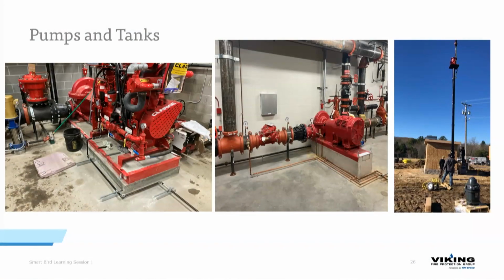On the left here we have a diesel fire pump. Again, extra consideration. Diesel, you need a tank. You usually need containment on that tank. You need exhaust. You need batteries for startup. You need a diesel mechanic there on a yearly basis to change the oil. Every fire pump requires some level of testing, and it could be weekly, it could be monthly. It's whatever the fire pump manufacturer really deems is what you need to do.